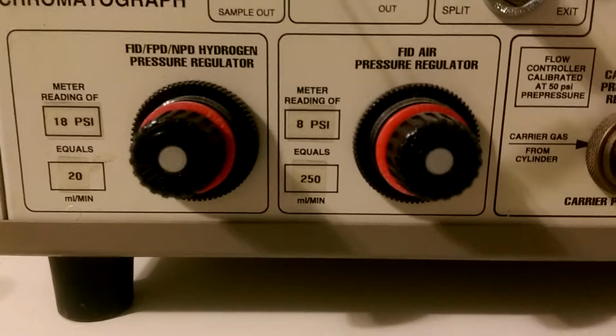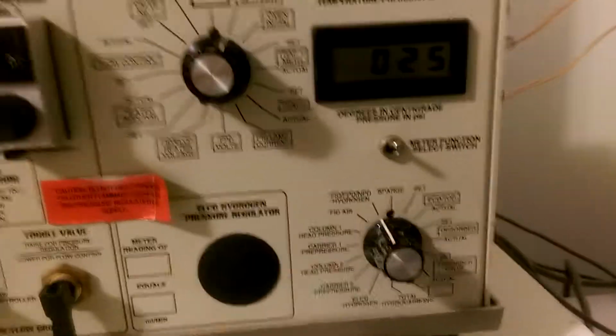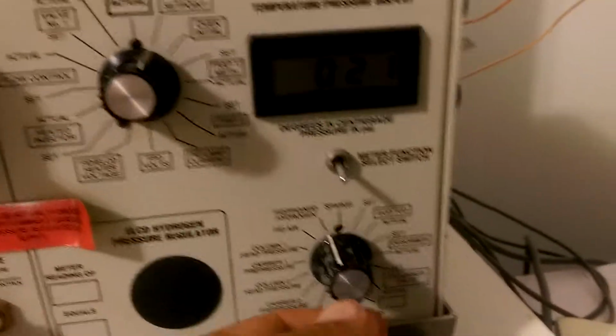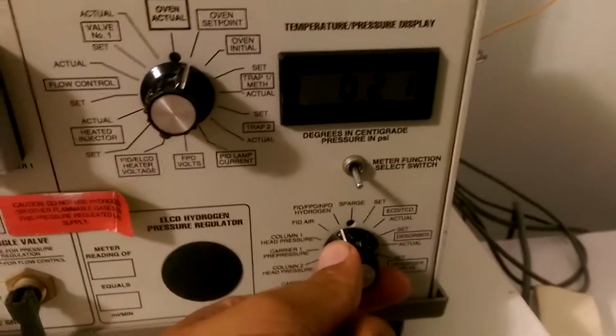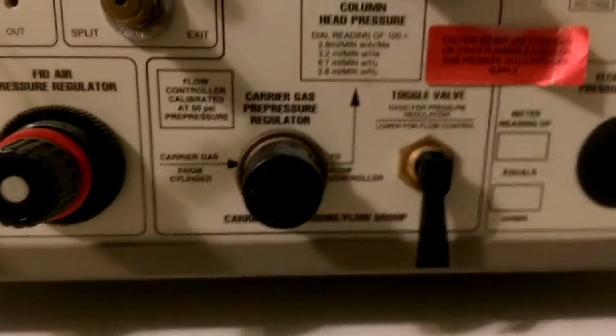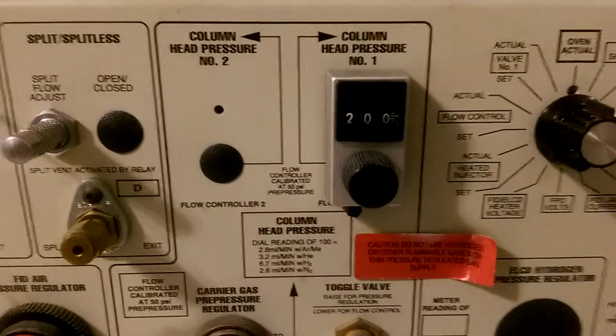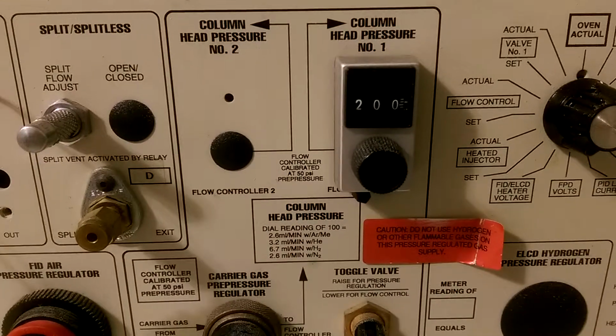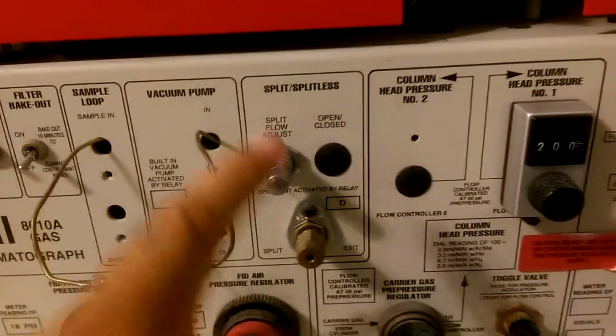We also have regulation for the air and for the hydrogen on the unit. These dials can be changed, and by looking at the pressure regulation here on this meter, we can check the pressure and change it to whatever we need to. Next to it is the carrier pre-pressure regulator, followed by the column head pressure gauge and adjustment regulator. And next to it is also the split flow adjustment and the split flow vent, because this unit also has a splitless injector.